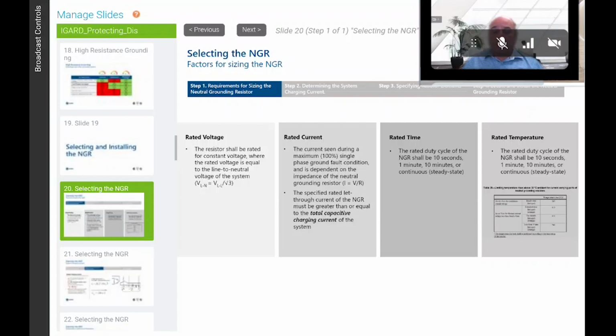Then you have to introduce a time. Now you're basically coordinating your protection system with the time. So if you can trip in 2 seconds, 3 seconds, remember, you want to allow some time for your system to differentiate which feeder has the fault, to which circuit you want to trip. So you could play with time to coordinate your protection system so that the faulted feeder will trip. The temperature comes with the time.